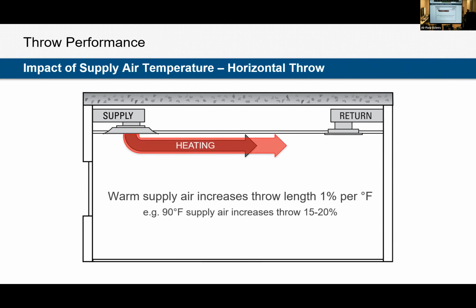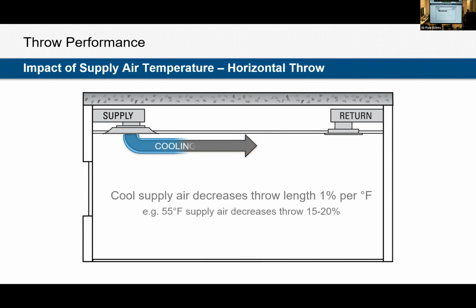In heating, if you're heating horizontally across the ceiling, you're going to get a throw length that is longer than what is cataloged. That's because hot air likes to stay high and hug the ceiling. So the rule of thumb is a 1% increase per degree difference. So if our space is 75 degrees, we're supplying 90-degree air, you're going to see a throw increase of about 15 to 20%. So in heating, it will get longer. What happens in cooling? It's shorter. The exact same rule of thumb is true: 1% decrease per degree difference in temperature. So our throw length in cooling is shorter than what is cataloged.